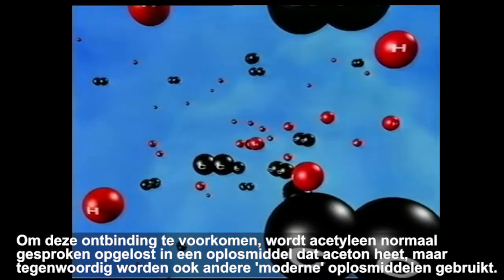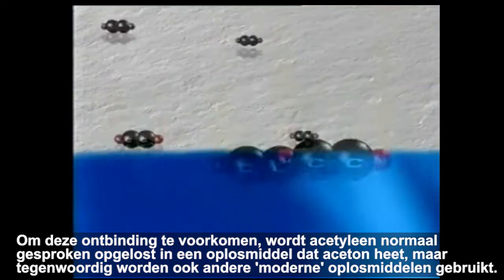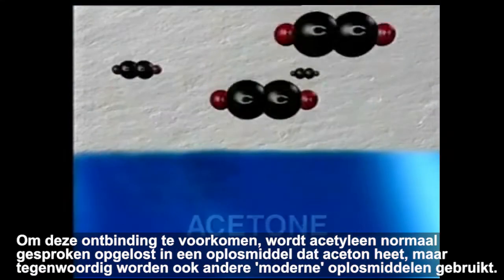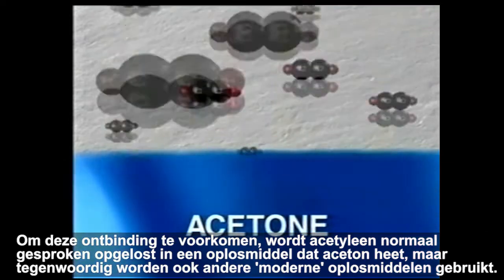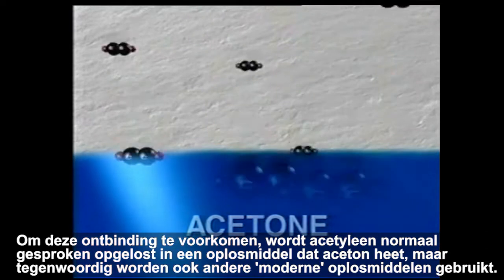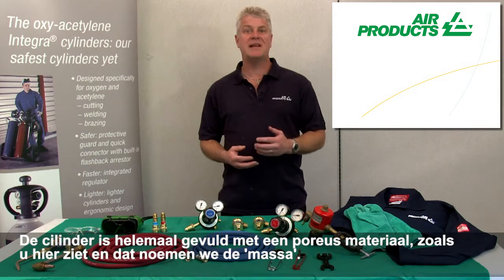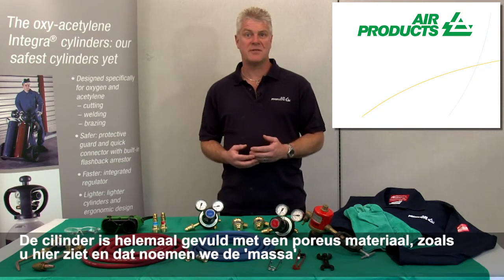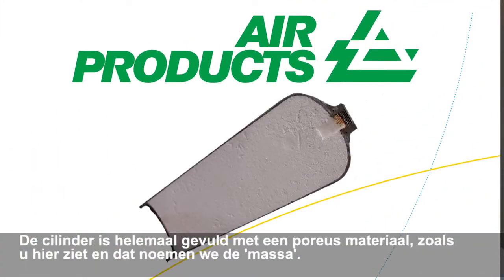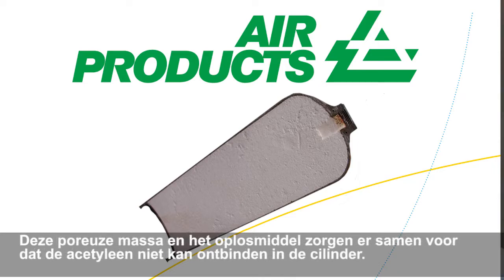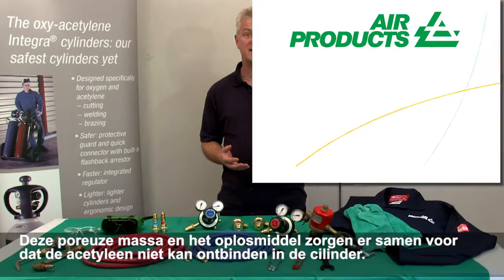To prevent this decomposition, acetylene is traditionally dissolved in a solvent called acetone, although other modern solvents are now also used. The cylinder is completely filled with a porous material like this known as the mass. The porous mass and the solvent work together to prevent decomposition of acetylene inside the cylinder.